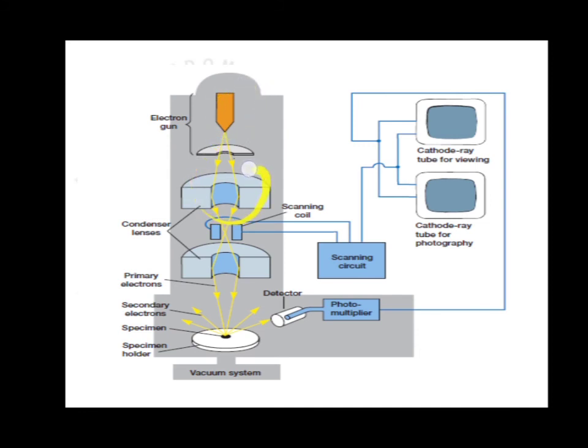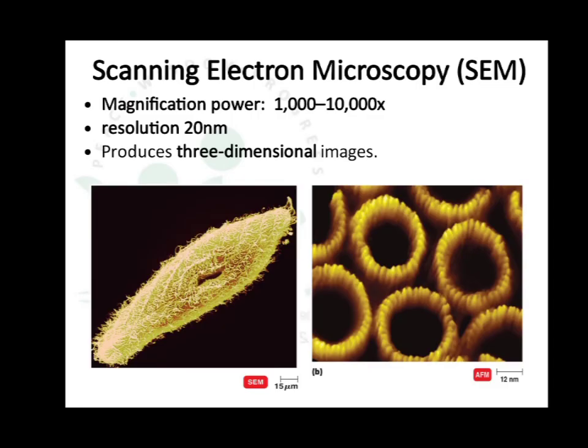The construction of the scanning electron microscope: there is an electron source, and the electron beam is focused by a condenser lens. Between the condenser lenses there is a scanning coil, and the beam is focused onto the specimen in the specimen holder. Primary electrons bombard the specimen and emit secondary electrons. These secondary electrons are detected by a photomultiplier tube connected to a cathode ray tube for viewing, as well as a cathode ray tube for photography.